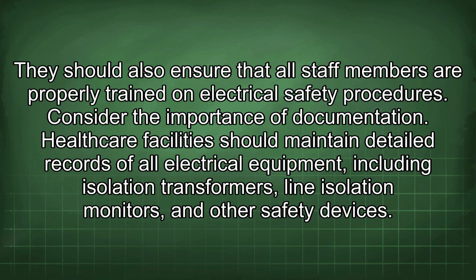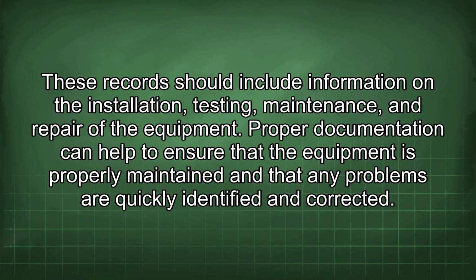Consider the importance of documentation. Healthcare facilities should maintain detailed records of all electrical equipment, including isolation transformers, line isolation monitors, and other safety devices. These records should include information on the installation, testing, maintenance, and repair of the equipment. Proper documentation can help to ensure that the equipment is properly maintained and that any problems are quickly identified and corrected.